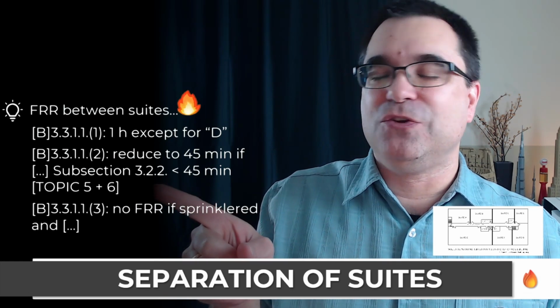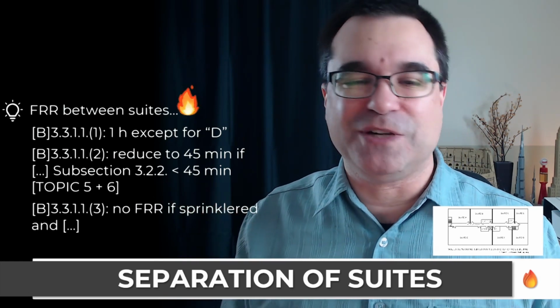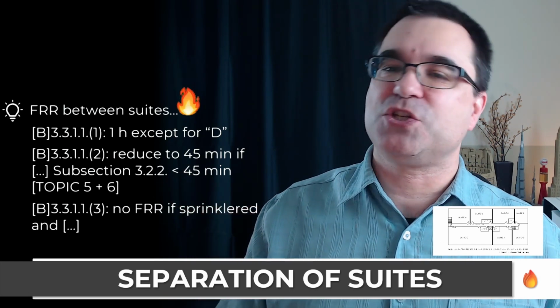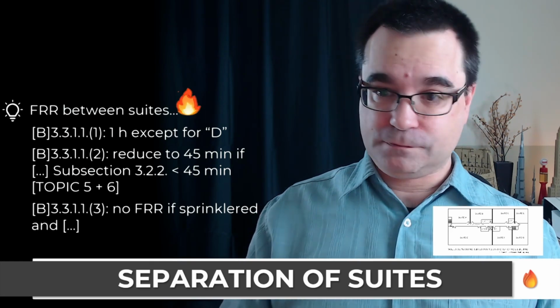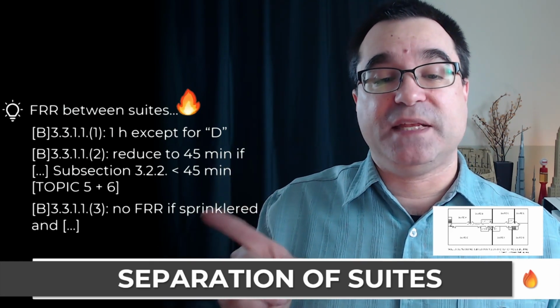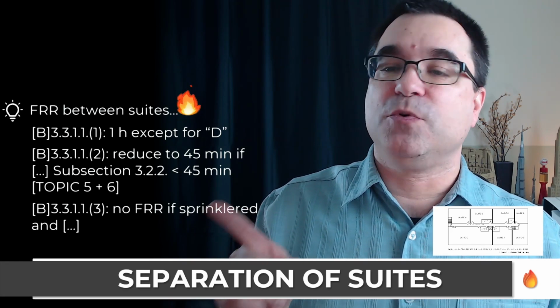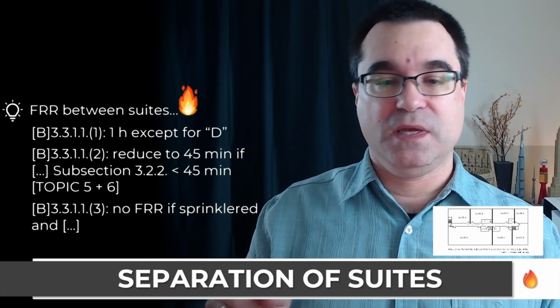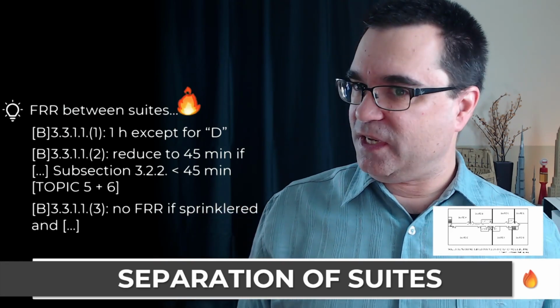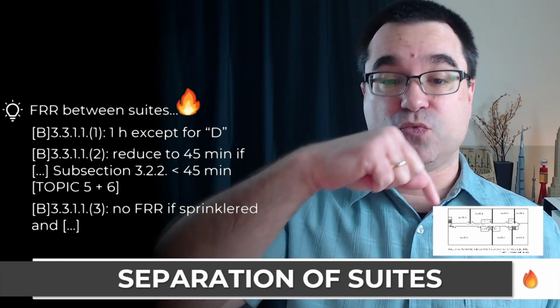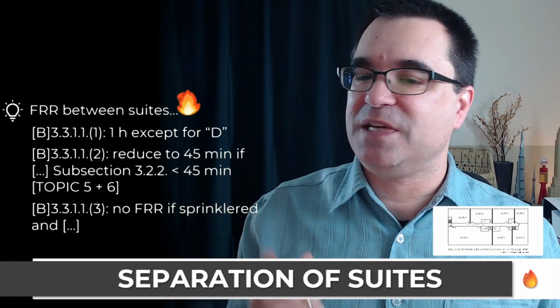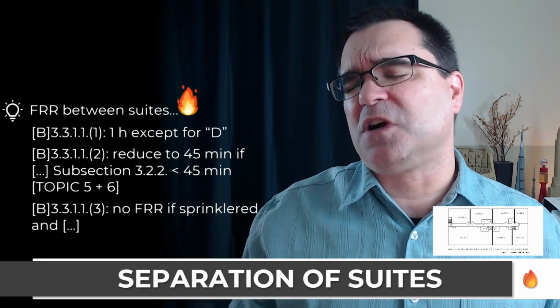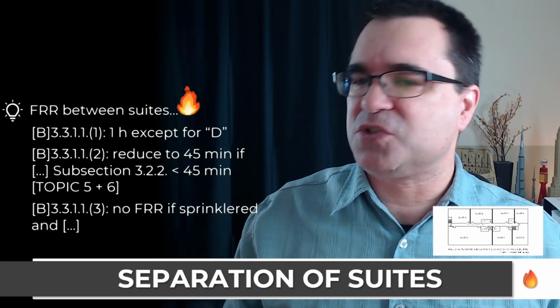And I would invite you to go check out topics 5 and 6 about this. That's where we covered subsection 3.2.2. Finally, under sentence 3, that is 3.3.1.1.(3), no fire resistance rating is necessary between suites as long as that space is sprinklered, and there are some other requirements for this. So go check it out, okay?